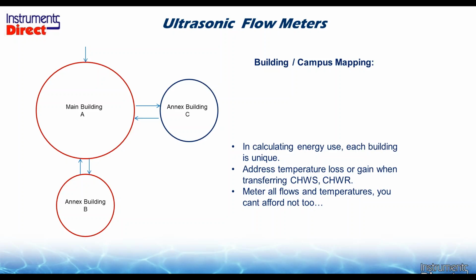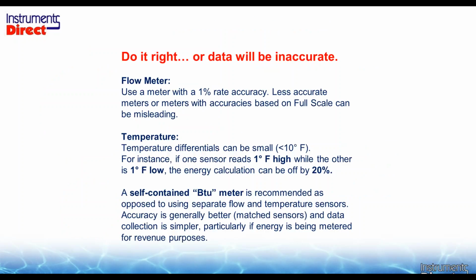Building B, we found out, transferred its chilled water subterranean from Building B to Building A, under the ground. And this was in a warm climate environment. Building C transferred its chilled water on a raised catwalk outside in the warm Florida sun. So it was exposed more to the external environment, and had an effect on the overall energy cost. Every little thing plays a role. As we get deeper into this, you can find out that every little bit of difference can make a dynamic effect on the energy monitoring of your application.